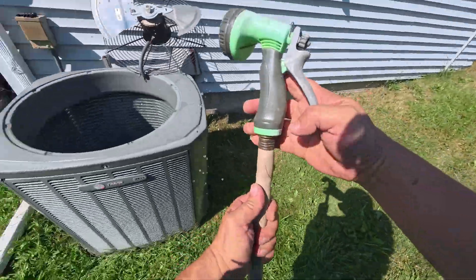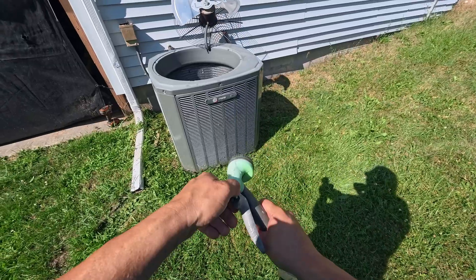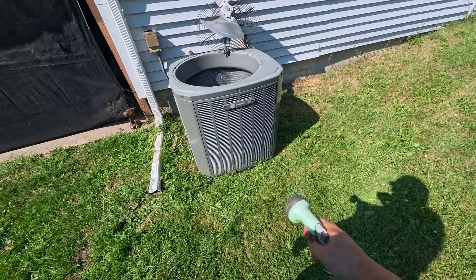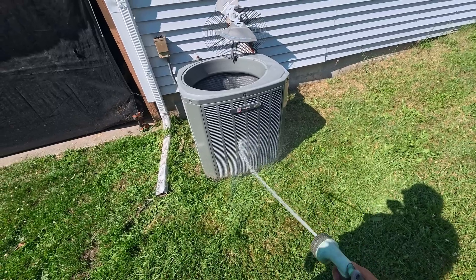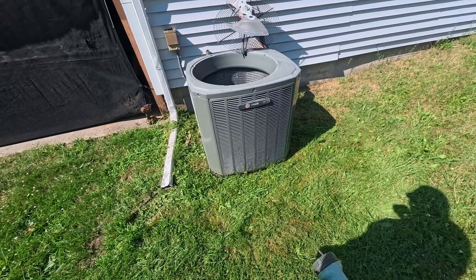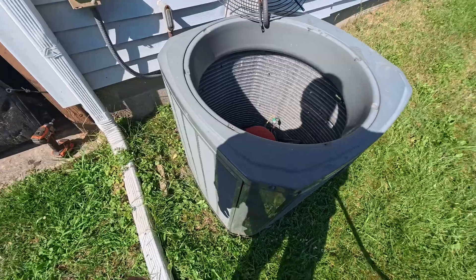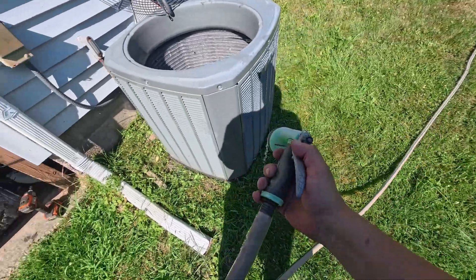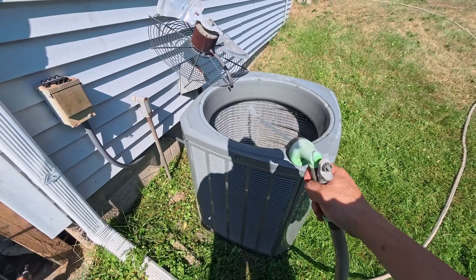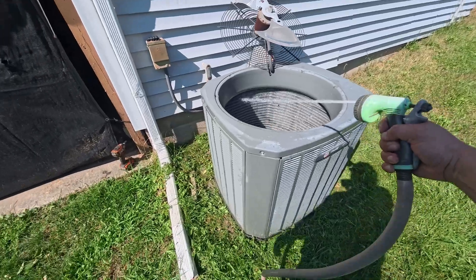These AC units, they suck air in from the outside and blow it out the top. So sometimes if you try to rinse them out from the outside in - and you can see how dirty that water is - you're just pushing dirt from the outside in. So if you can blast it from the inside out, it usually cleans it better.